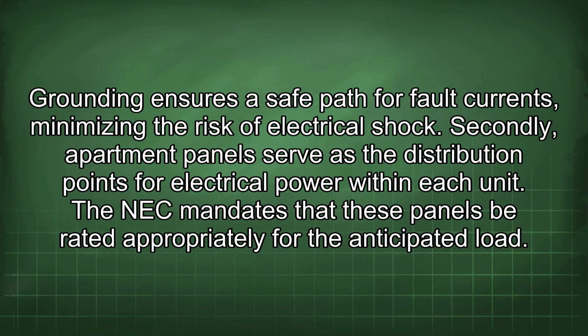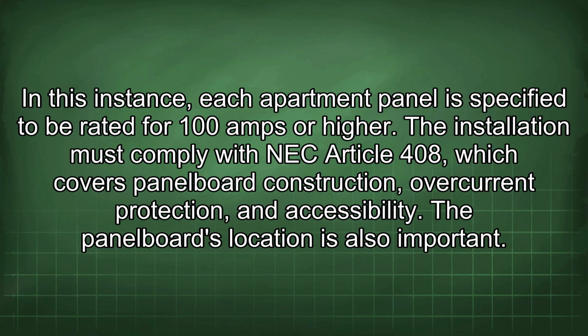Secondly, apartment panels serve as the distribution points for electrical power within each unit. The NEC mandates that these panels be rated appropriately for the anticipated load. In this instance, each apartment panel is specified to be rated for 100 amps or higher. The installation must comply with NEC Article 408, which covers panel board construction, overcurrent protection, and accessibility.